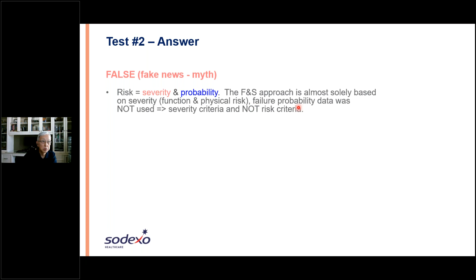what the concept of risk is today. Risk is composed of severity and probability. The Fennigkoh model is basically based on severity. It's a function of physical risk, and the probability data was not available and was not used at that time, and it continues not to be used today. Your scheduled maintenance, PM, is primarily determined by the technology used in that device and not by the severity or even risk of that piece of equipment.